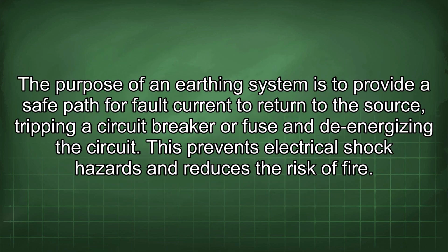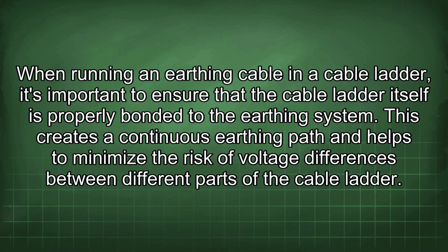The purpose of an earthing system is to provide a safe path for fault current to return to the source, tripping a circuit breaker or fuse and de-energizing the circuit. This prevents electrical shock hazards and reduces the risk of fire. When running an earthing cable in a cable ladder, it's important to ensure that the cable ladder itself is properly bonded to the earthing system.